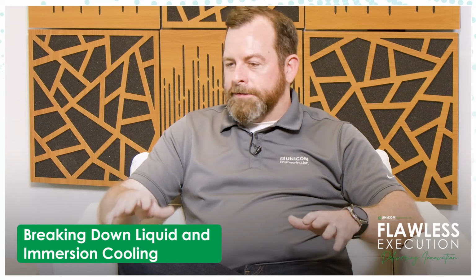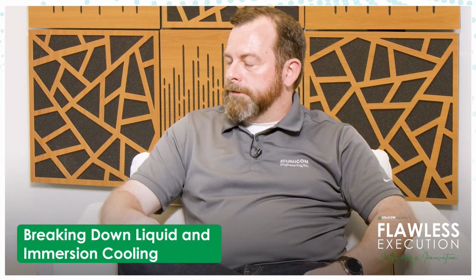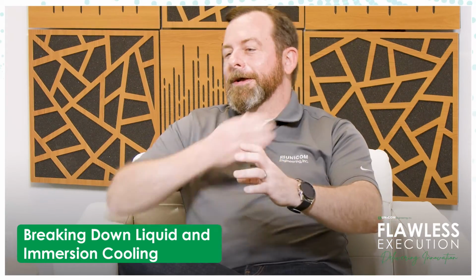Additionally, our CPUs keep getting hotter, accelerators keep getting hotter, they need more power. Right now top of the line chips from Intel and AMD are 270, 280 watts, very quickly moving to 350. Looking ahead a couple of years, 500 to 700 watts per chip is extremely possible and will be coming. You simply cannot cool those with traditional air-cooled heat sinks in the form factors that exist today. You have to go bigger and bigger, so a 1U server might have to become a 2U server or even bigger, because you need that bigger hunk of metal to blow more air through to cool a 350, 400, or 500 watt CPU.